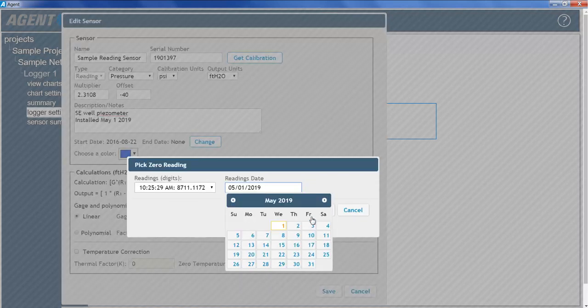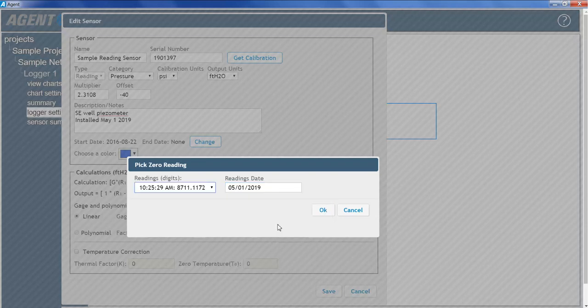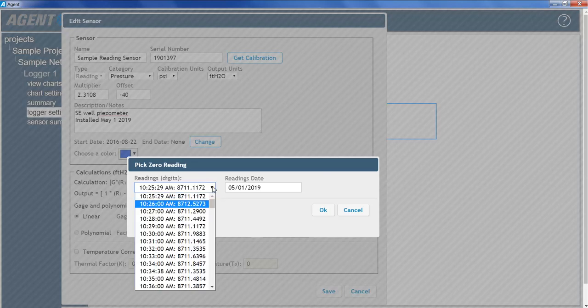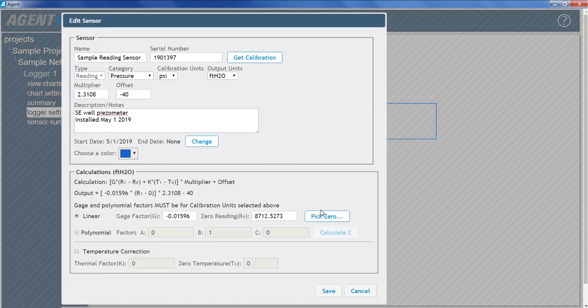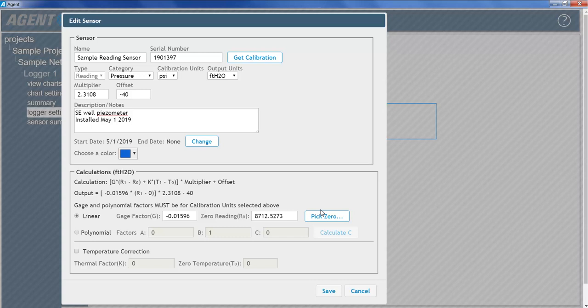Select the date the initial zero reading was taken. Then select the applicable reading from the list. And then click OK. It is very important to enter an accurate on-site zero reading. This reading will be used for all subsequent data reduction. Make sure to prepare the sensor for the reading as described in the sensor manual. Consult the sensor manual for more information on establishing an initial zero reading.